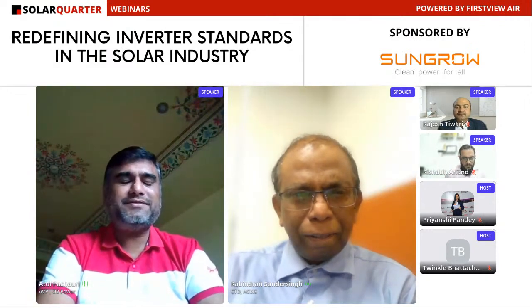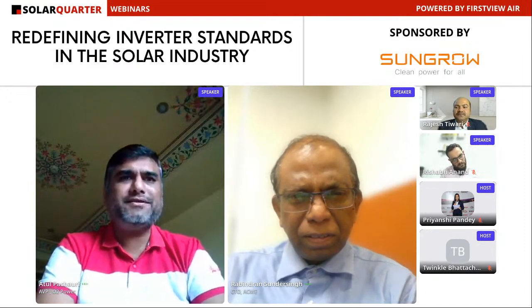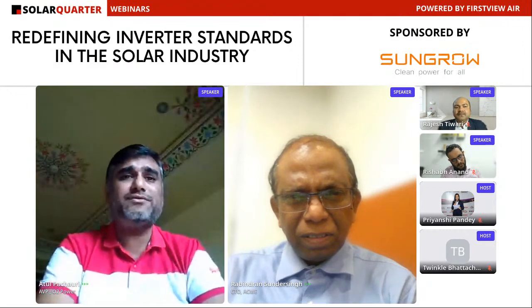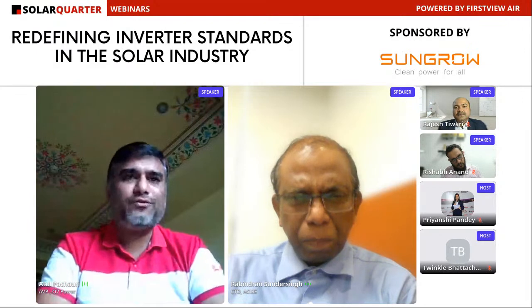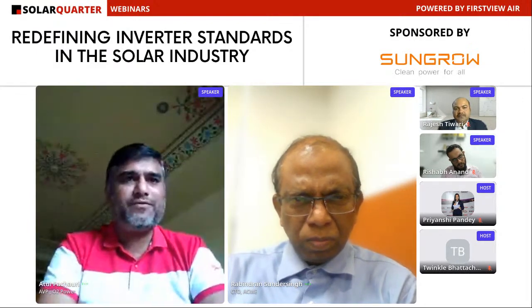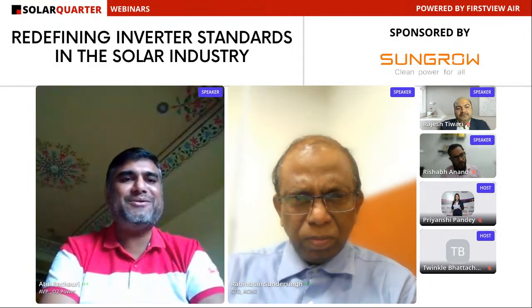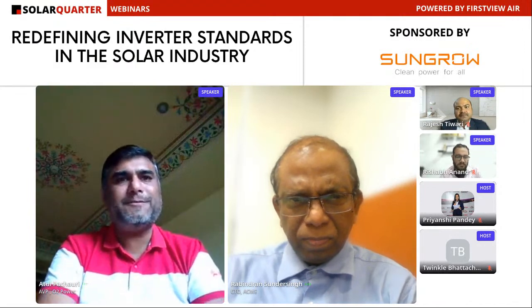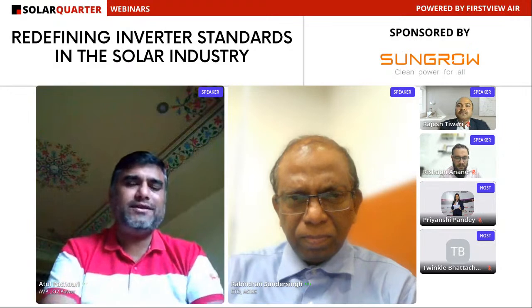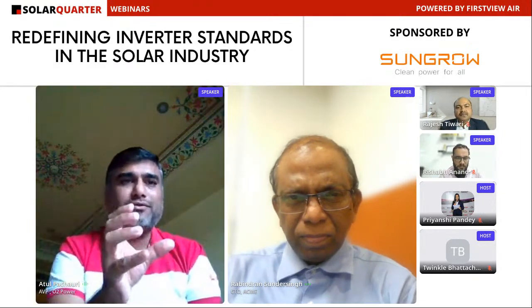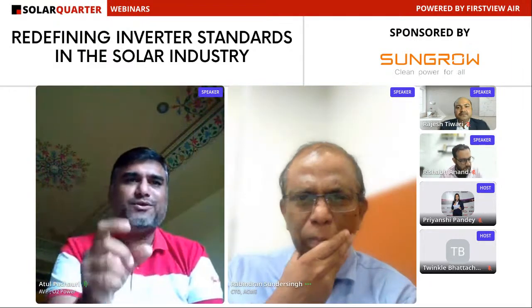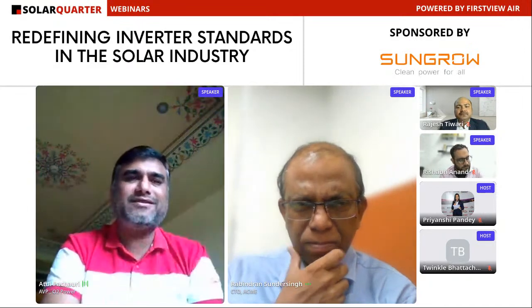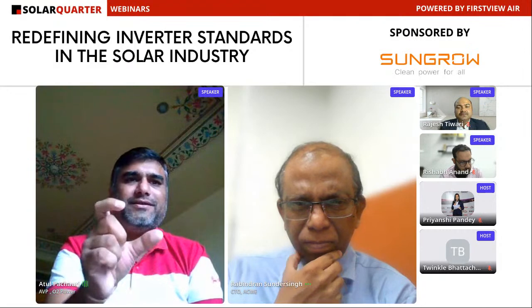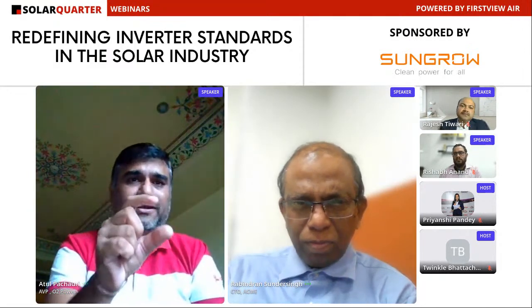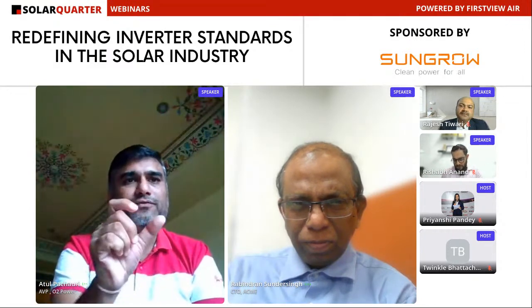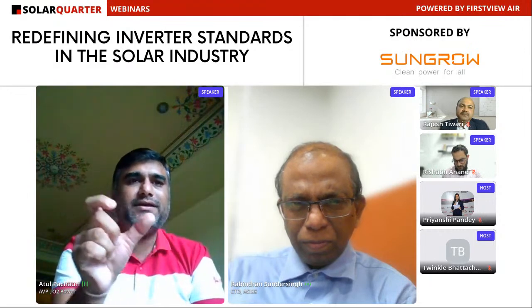Rightly said, Ravindran sir, because people may or may not acknowledge that for the first few weeks, say 5 or 6 weeks, during the stabilization time, we are losing a lot of energy, not reaching our top performance, and nobody knows how many strings are under breakdown and where they're located, because nowadays we aren't choosing string monitoring, everybody is going with SCBs only. During that phase, if we can give a proper weightage while modeling the cost, since cost is the prime governor for selecting string or central inverters, this is a very good topic that modeling people should put a weightage for the first few weeks of energy loss. This is really interesting.